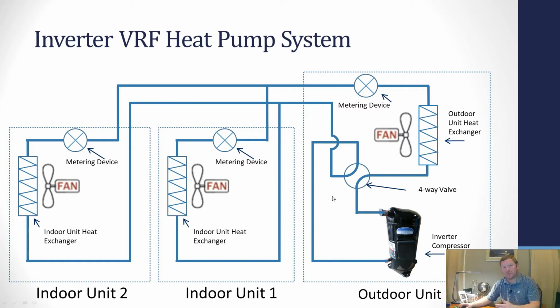So you always want to be maintaining whatever your set point comfort level is, just leave it there. The nice thing about the VRF though is when that room temperature drops 1 degree, it'll call, and it'll do its best to maintain that set point with no offset. If for any reason it gets 1 degree past the set point, it goes thermo off. It says, hey, I don't want any more heat. Turn the fan off if you want to turn the fan off, or go to low and just ramp down as far as possible. And so now I can have indoor unit 1 have its fan turn off, and now my living room just stays 70 degrees. And indoor unit 2 that still needs to heat a couple more degrees can do so.